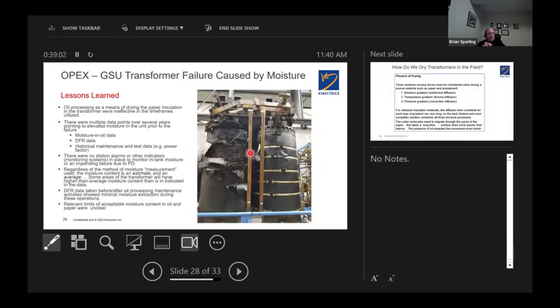There were no alarms from a monitoring system indicating the moisture was coming out of the paper and back into the oil. And whatever you're using, it's an estimate and it's an average. But the important thing is they didn't dry the paper. They assumed that once the oil was dry, we're good. And that was not the correct decision to make. And acceptable limits of moisture content in the oil and paper were unclear to them.